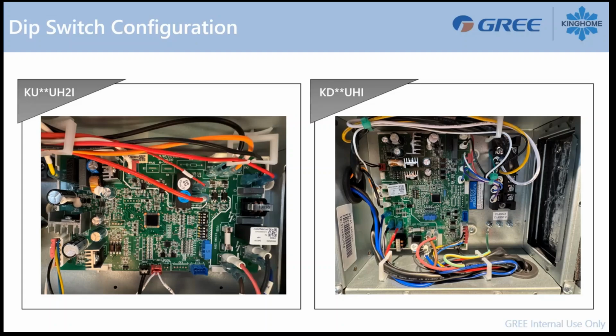When we are taking a look at the board itself inside the air handler, you have some dip switch configuration to do if you want to change the fan speed or your static pressure adjustment and this kind of stuff. So on a KU, there's two blocks here of dip switch, but only the top one will be in use. So you have this block here called SA2. So this is the dip switch block SA2.